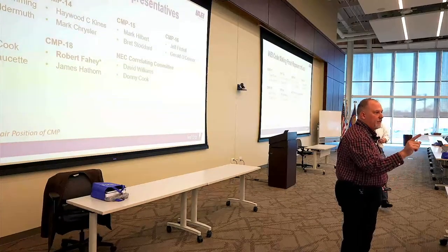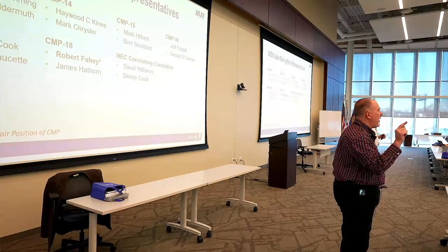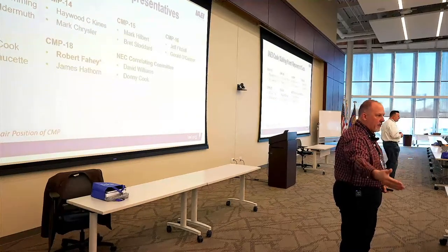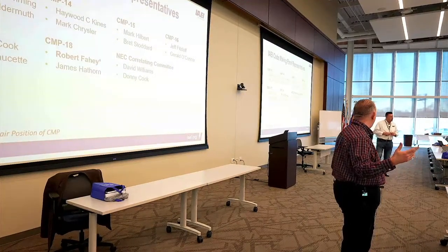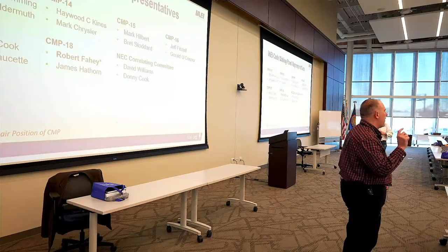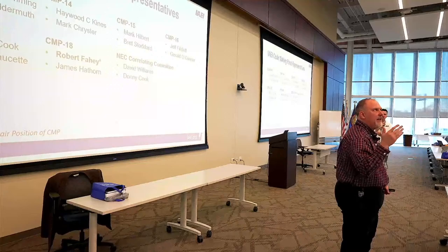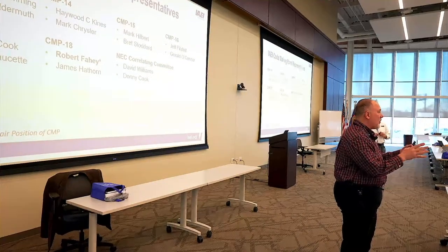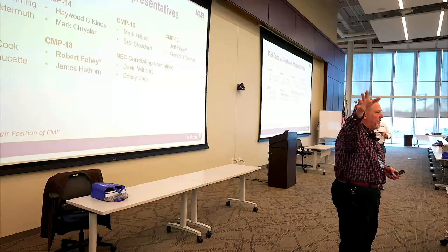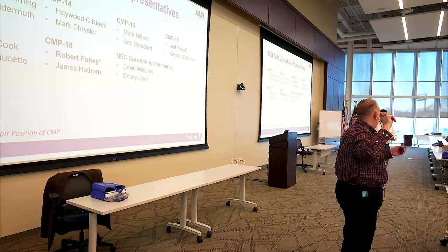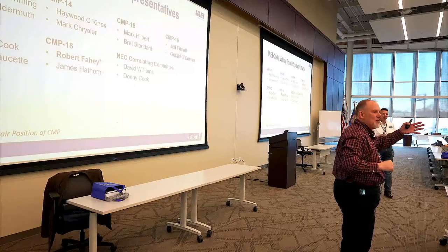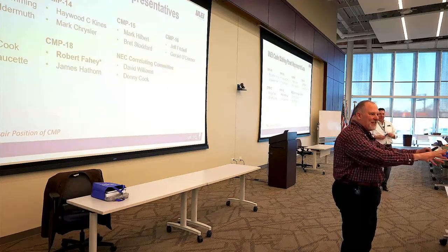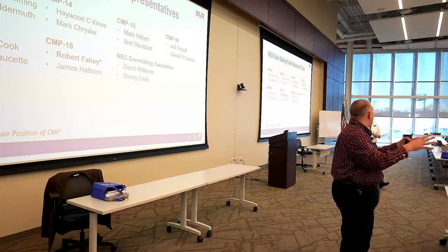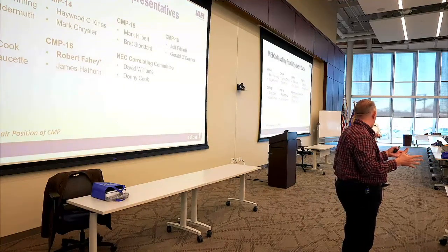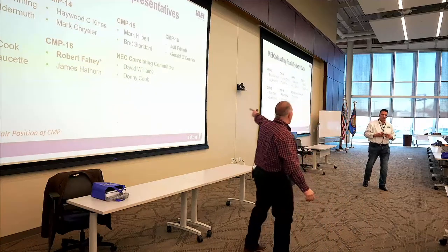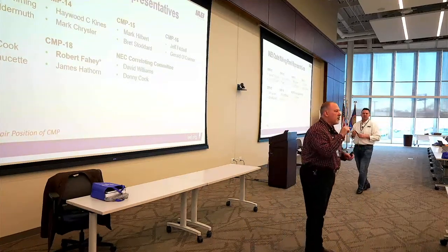A good example is GFCI protection. With 210.8(B), for other than dwelling units, that didn't exist until the 1990-something code. There was an edition where they created 210.8(B), and before that, if it wasn't a dwelling unit, where did we go? Back of the book, Chapter 6, Chapter 5 for healthcare, 555 for marinas, and RV parks. Then we created 210.8(B) and kept it at 15 and 20 amp receptacle outlets, then expanded it beyond that, creating a conflict with the chapters in the back of the book. The correlating committee recognizes those, hopefully sooner rather than later.